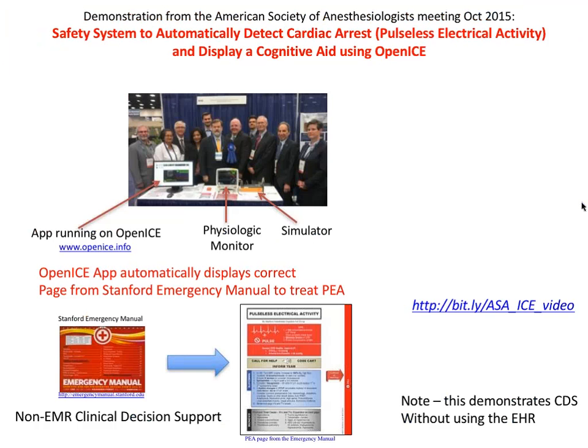An example of how to use OpenICE to improve safety is a demonstration we had at the American Society of Anesthesiologists in which we ran OpenICE to look at data in real time, detect a cardiac arrest, and then show information to help the clinician treat the patient. As a group, we didn't have to think and work on the specific treatment protocols — we simply linked to a widely accepted source, the Stanford Emergency Manual. By using apps running on OpenICE, we're able to enhance vigilance with continuous monitoring and no false alarms.